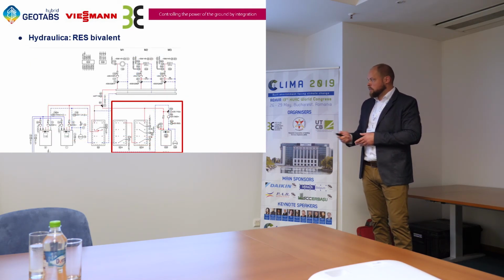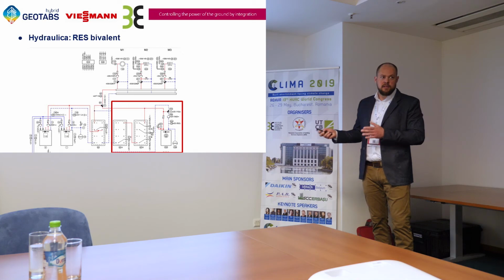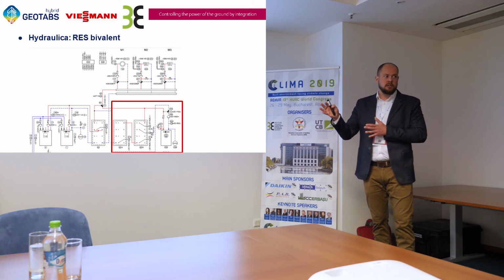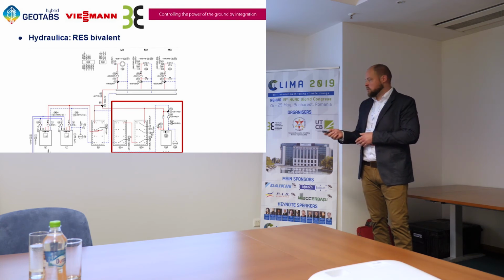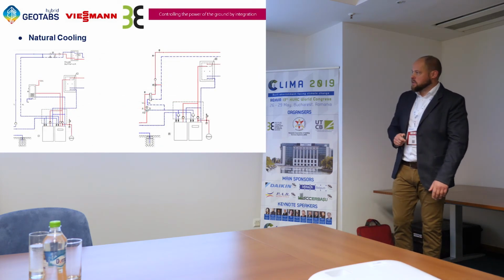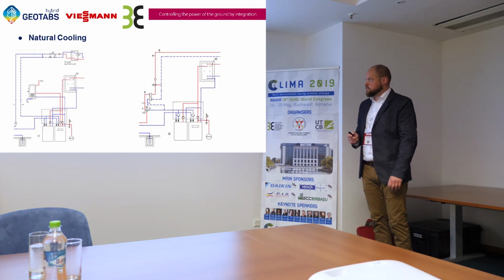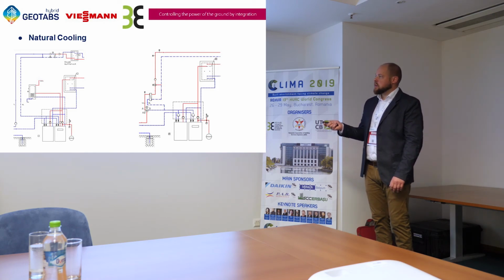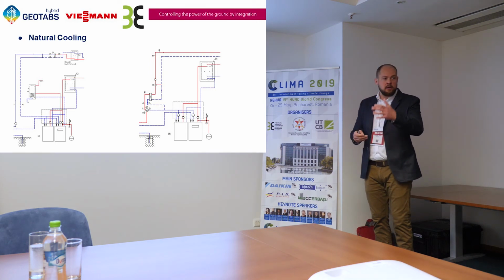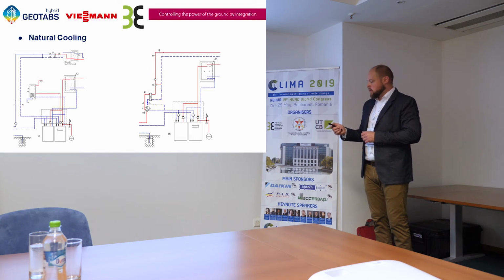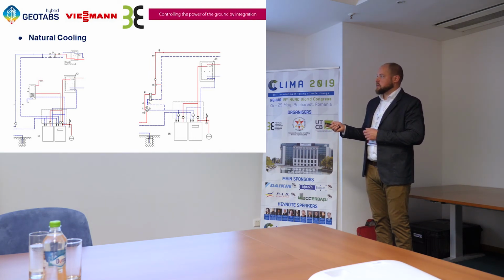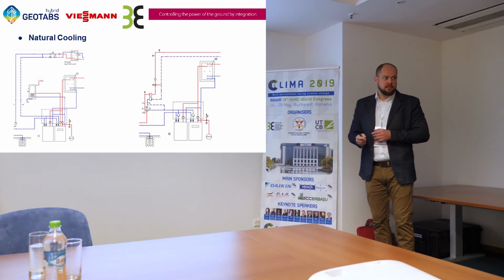This is biomass, for example. This has its own buffer tanks, because there it's different. We have 50 liters per kilowatt up to 100 liters per kilowatt, depending on how the biomass system works. Natural cooling is another aspect that we can do with the geothermal source in this project. So we have a heat exchanger here connected to the source, and with this heat exchanger we can circulate temperatures of about 10 degrees, for example, throughout the building. Sometimes we have to use a cooling buffer tank. Mind the connections here, it's not like a normal buffer tank, sometimes that's done wrong.